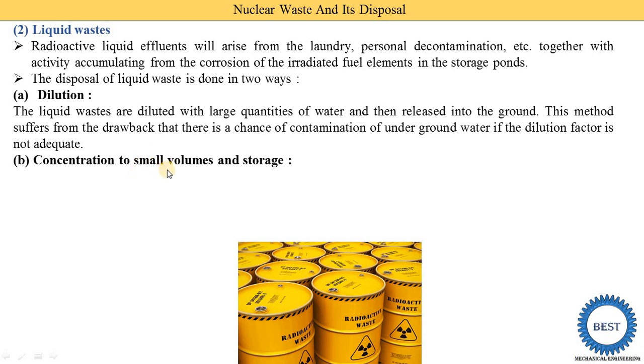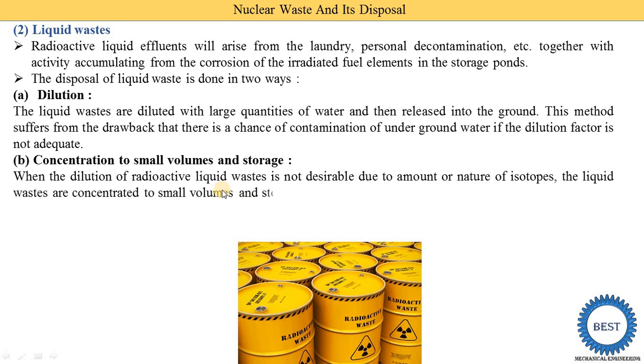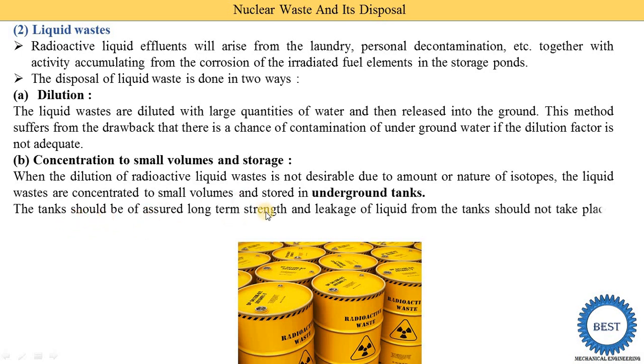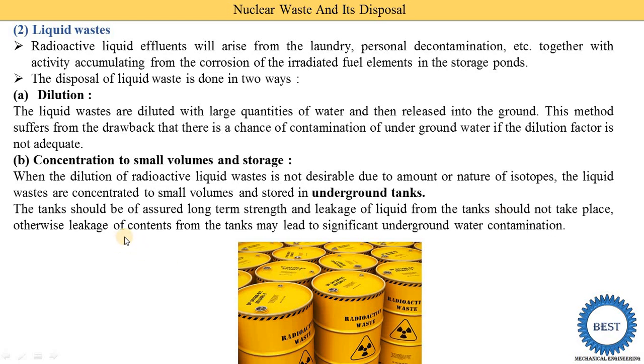The second method is concentration to small volumes and storage. When dilution of radioactive liquid waste is not desirable due to the amount or nature of the isotopes, the liquid waste is concentrated to a small volume and stored in underground tanks. The tanks shall be of assured long-term strength, and leakage from the tank shall not take place; otherwise leakage of contents may lead to significant underground water contamination.